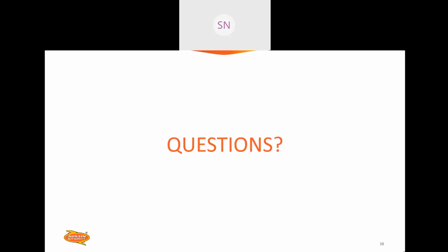Sean says, can you go into more detail why we need to be on site for the inspection for an Enphase setup? Rory, I pass that one to you. Okay, that's a good question. Sarah, that was one thing that we need to take off the list there. I'm sorry I didn't let you know about that earlier. In-phase is microinverters, and they don't need to be present unless something's really wrong. Generally speaking, they don't need to be there for microinverters, only for single inverter systems, because I don't know how to operate half of those things that are out there. So to answer your question, no, you don't have to be out there for microinverters, which is what Enphase is, correct?